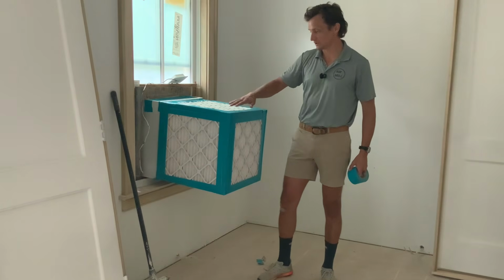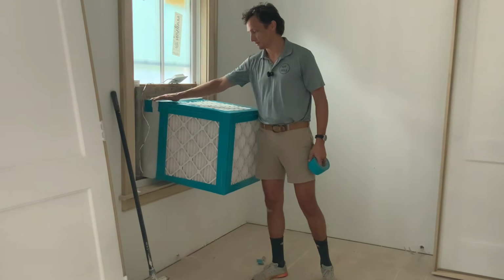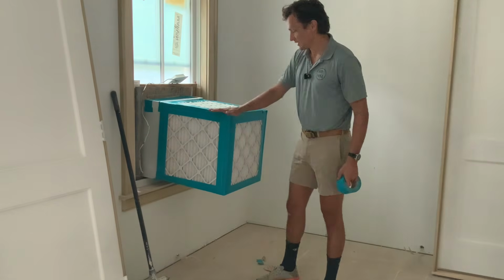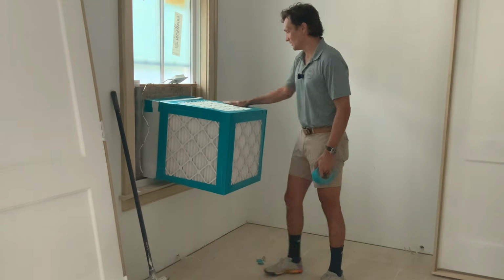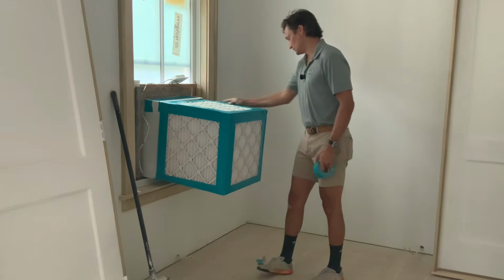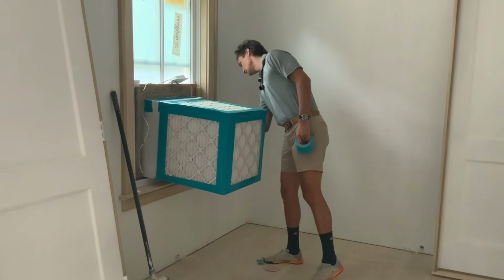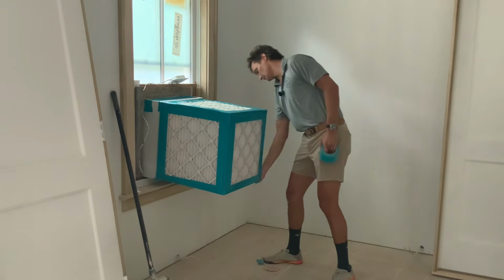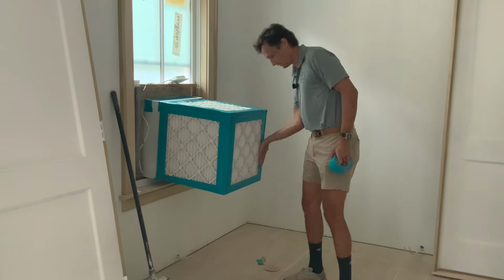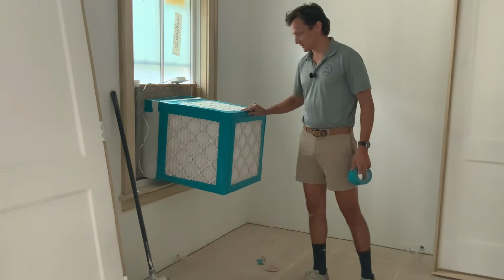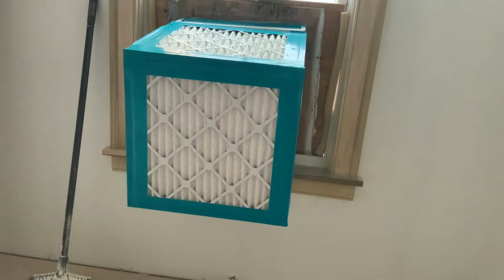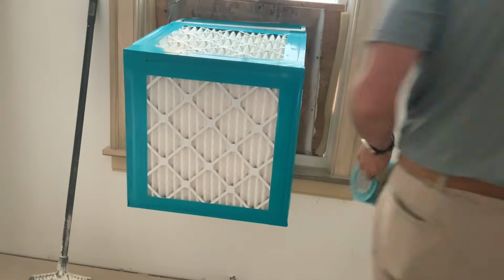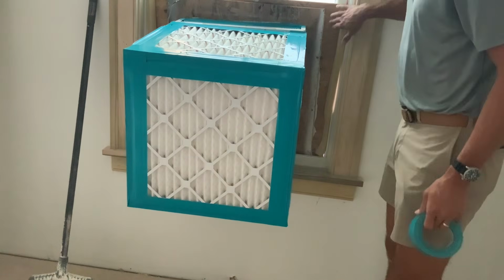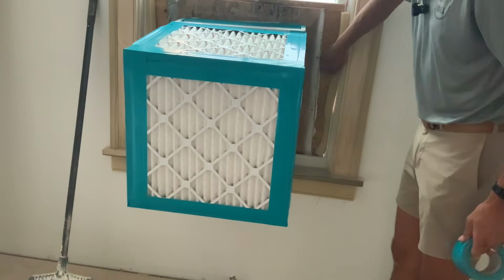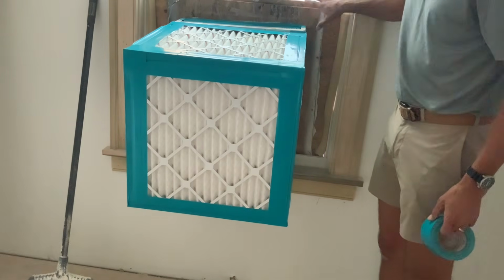So once you put the duct tape on, you've got to go around by hand and make sure that every filter, the duct tape is well adhered to the filter and well adhered to the filter box. An airtight seal with the duct tape is critical. The next part of the filter change process is making sure that all of our window fittings are secure, that we're not having any water damage.